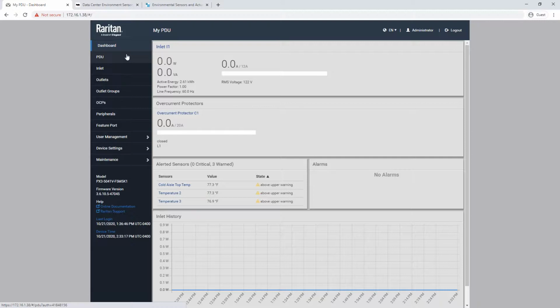A couple other things to note: if you're a PowerIQ user, there are thresholds within PowerIQ that are not part of the PDU. So you might get an alert in PowerIQ that says this temperature sensor is above a threshold, but really it's just an alert coming from PowerIQ, not actually a trap from the PDU. They're mutually exclusive — different thresholds, even though they're triggering off the same sensors.